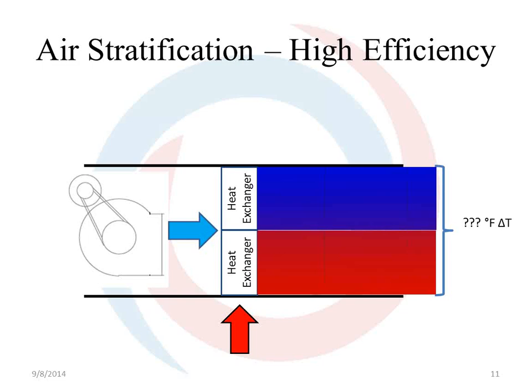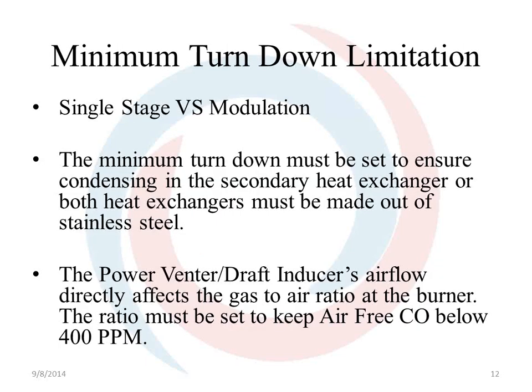A couple of the other problems is the staging. Single stage is limited in that it can only fire at 100%. In order to maintain a temperature set point, the unit has to rapidly cycle the burners. Each time a burner lights, it has what is called cycle loss, which lowers its efficiency when it first fires. This is due to the amount of gas that's released prior to ignition to ensure that the burner lights. With the modulating gas control, since the surface area is constant, the efficiency of the unit will improve as the firing rate is reduced.